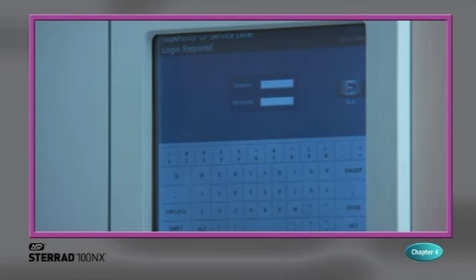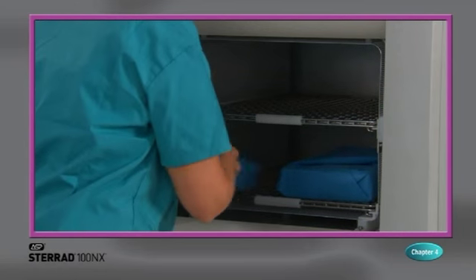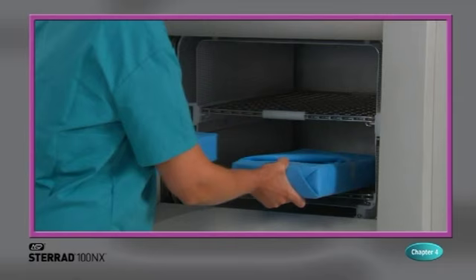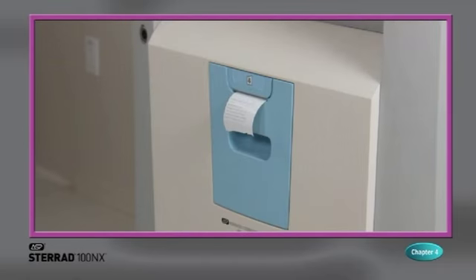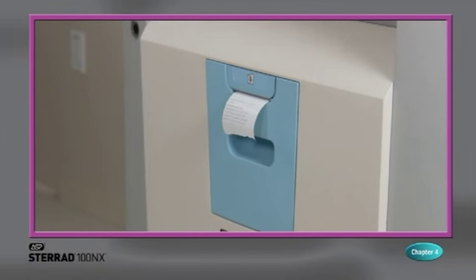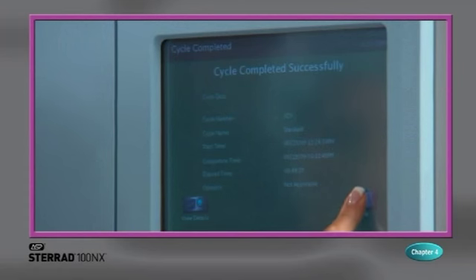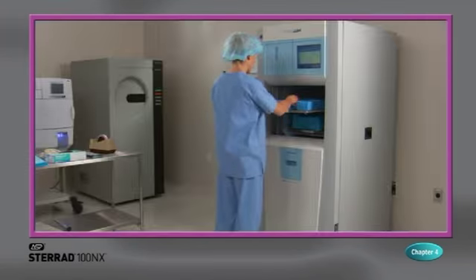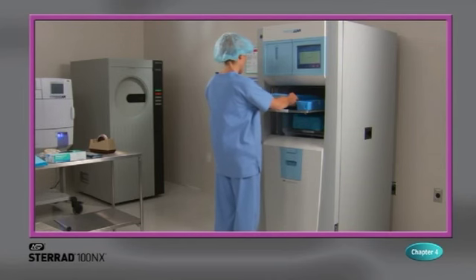If login is required before the door can be opened, the login screen is displayed. When this occurs, enter your operator identification and password and touch Enter. The door opens and the load can be removed. The operator's name appears on the printout acknowledging the completion of the cycle. If no login is required for load removal, the door opens and the load can be removed.